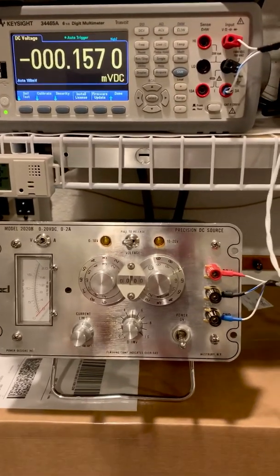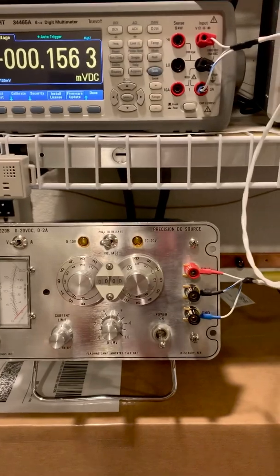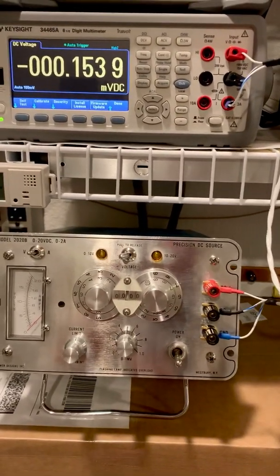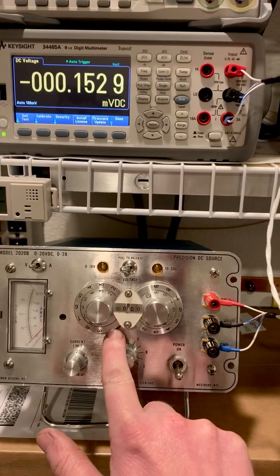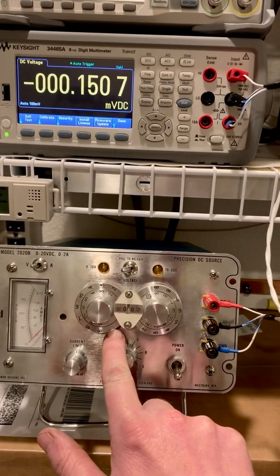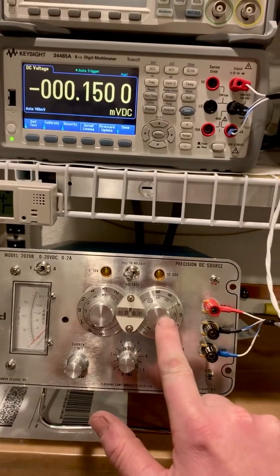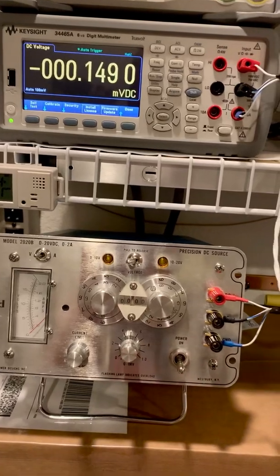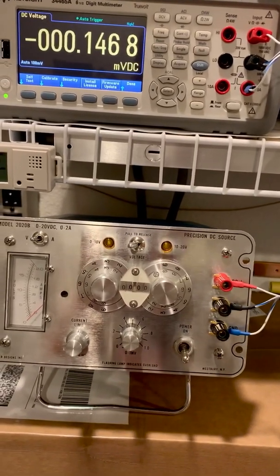The voltage is set by these decade dials: volts, 100 millivolts, 10 millivolts, 1 millivolt, and then a little vernier down here for 0 to 1 millivolt.